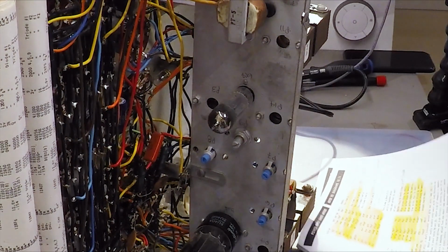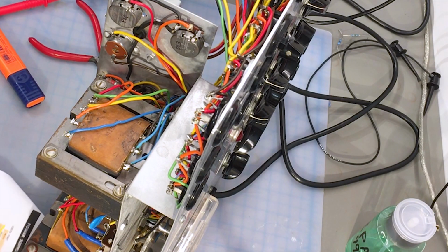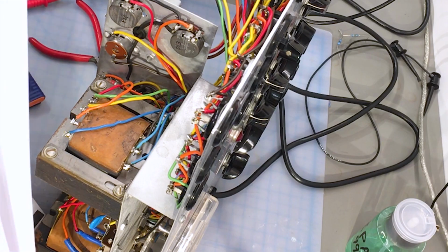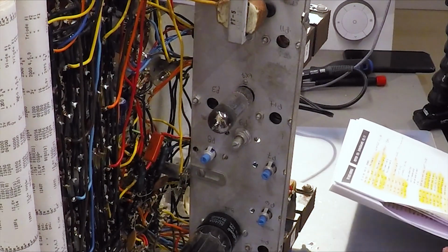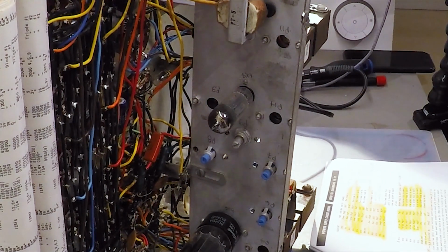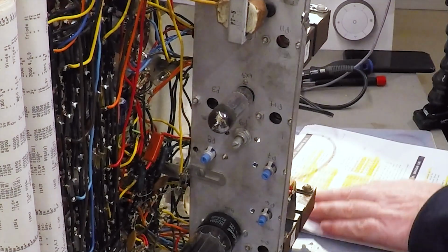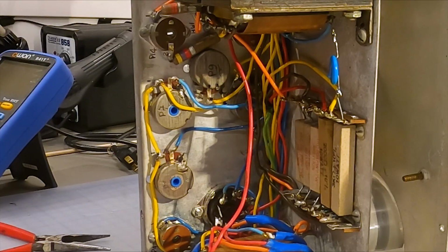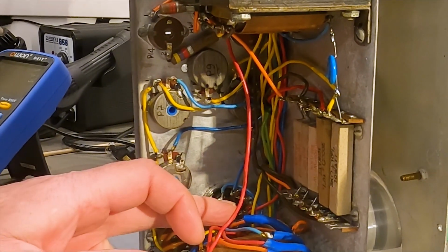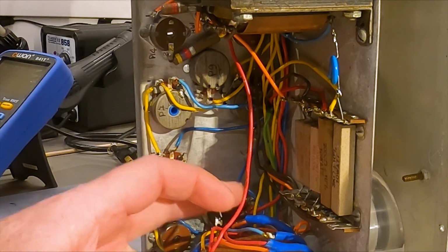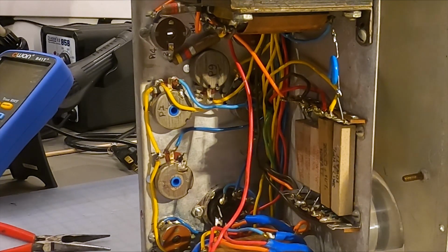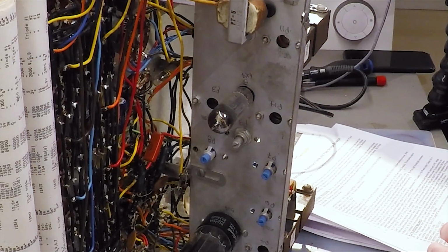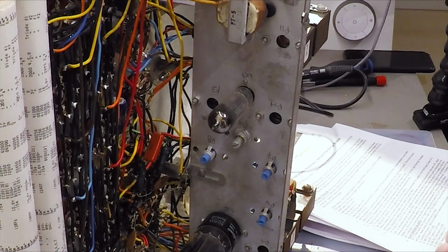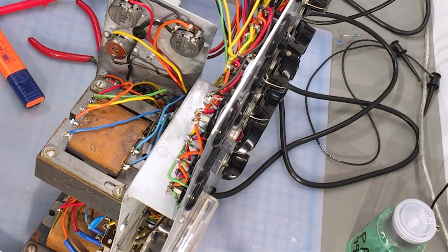So after a fairly comprehensive review of the wiring of this instrument, piece of equipment, tube tester, I have identified a number of out of specification components, mostly just resistors that have drifted. And I've replaced a few of these, and we'll replace a few more. But really the biggest area where I see discrepancies from the assembly instructions relate to some of the wiring around H1, which is the socket for the 5U4 rectifier. Some of that can be accounted for in some of the calibration instructions, which do suggest some rewiring of H1 in response to adjustments that may be required as a result of the phasing of this power transformer, PT4.